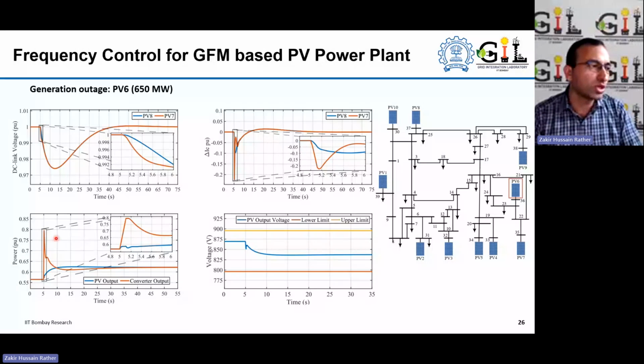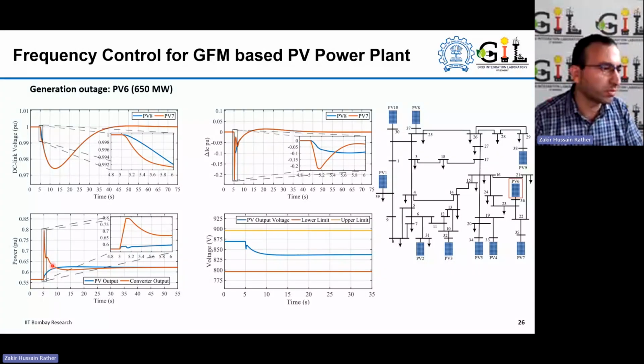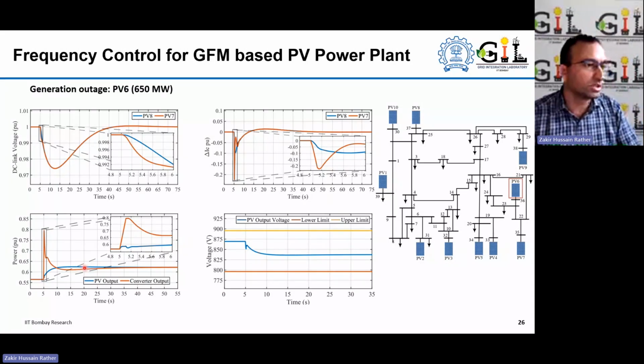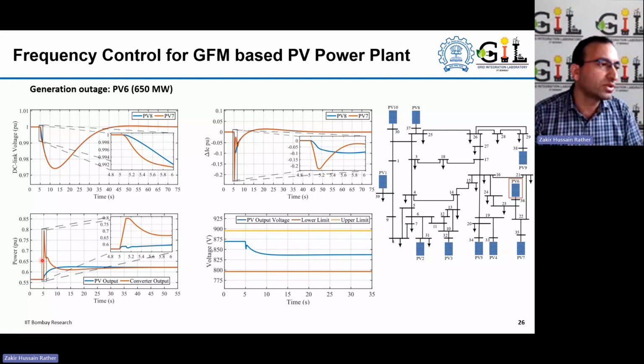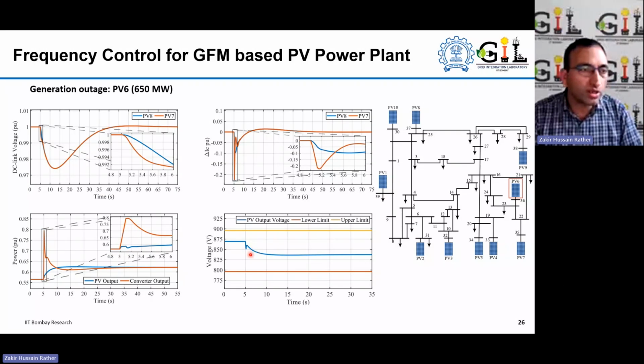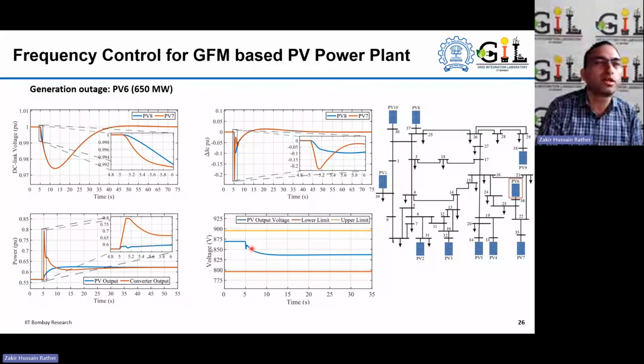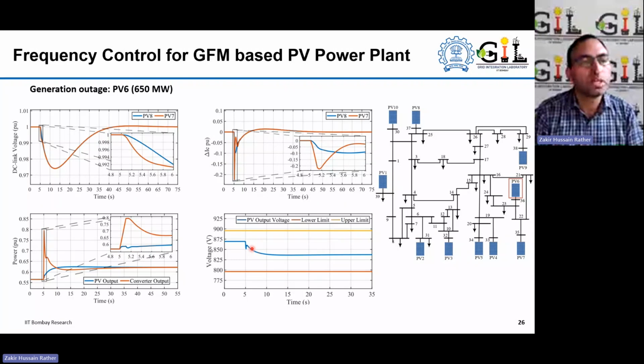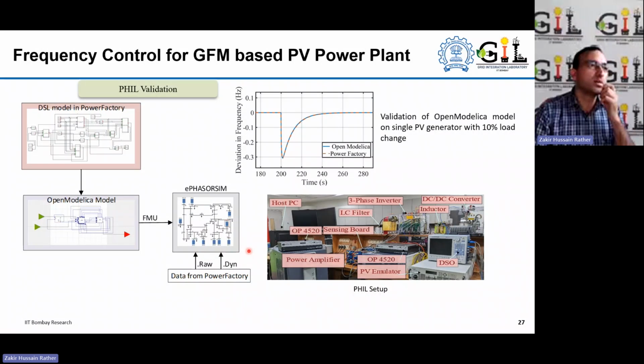So you can see here in the output of the power plant, this is power plant 7. This is the total power output of the converter on the grid side, whereas the blue one is the actual DC power output of the PV modules of this plant, which indicates that we are able to inject additional power here at the onset of the disturbance to provide inertial response to the grid. And the DC link voltage of the plant is actually decreasing. This is the upper limit, this is the lower limit, because the plant was operating on the high voltage side of the MPP before the event, and therefore once the event occurred, the voltage was reduced to provide this support.